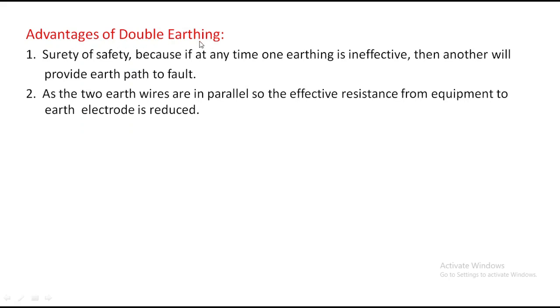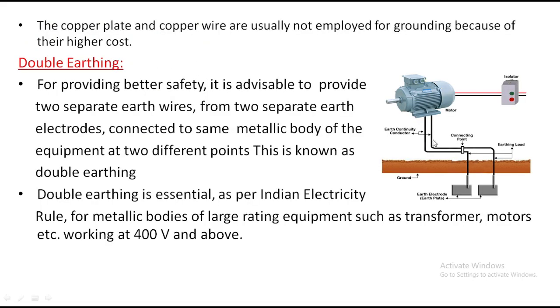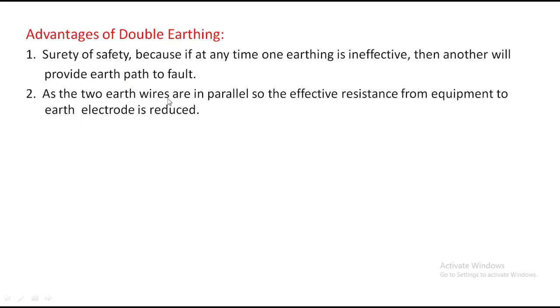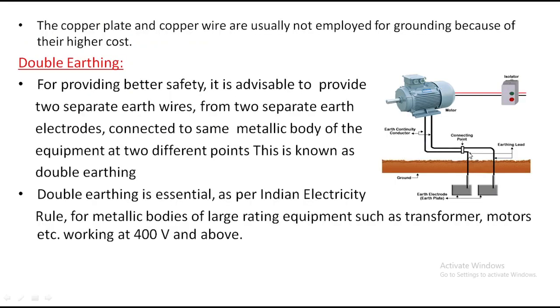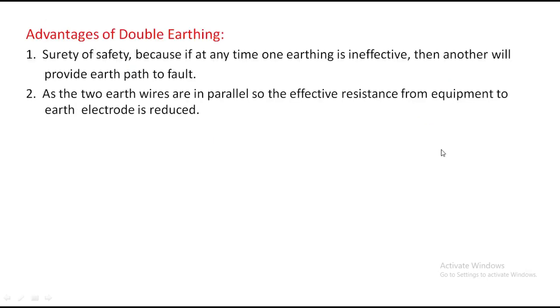We have some advantages of double earthing. The first point is surety of safety, because if at any time one earthing is ineffective, then the other will provide the earth path for the fault. Suppose this earth wire fails, then the leakage current will flow to this electrode. Second, as the two earth wires are in parallel, the effective resistance from the equipment to the earth electrode is reduced. Whenever two conductors are connected in parallel, the total resistance decreases, so more leakage current enters into it. This is the importance of double earthing.